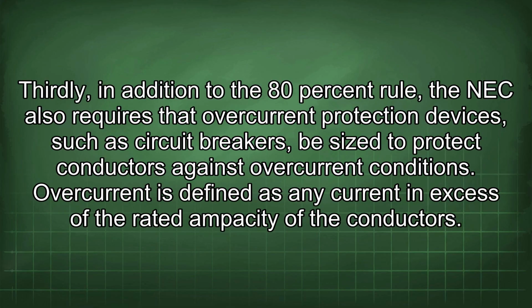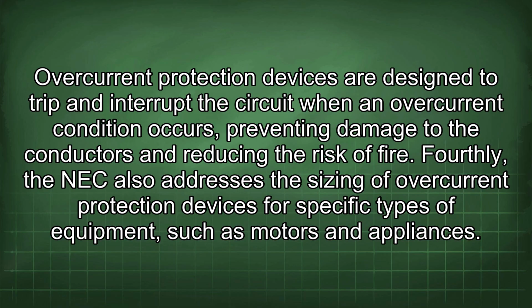Thirdly, in addition to the 80% rule, the NEC also requires that overcurrent protection devices, such as circuit breakers, be sized to protect conductors against overcurrent conditions. Overcurrent is defined as any current in excess of the rated ampacity of the conductors. Overcurrent protection devices are designed to trip and interrupt the circuit when an overcurrent condition occurs, preventing damage to the conductors and reducing the risk of fire.